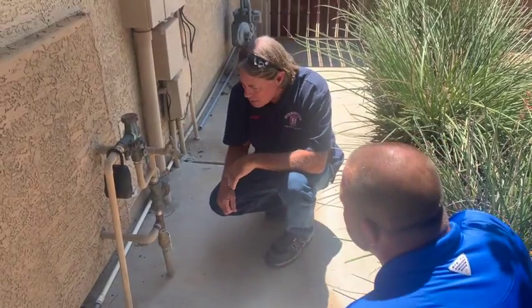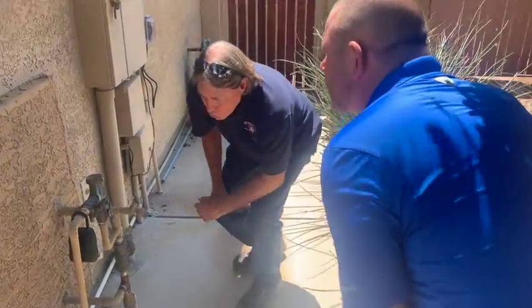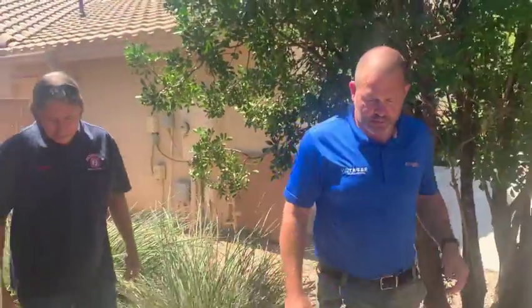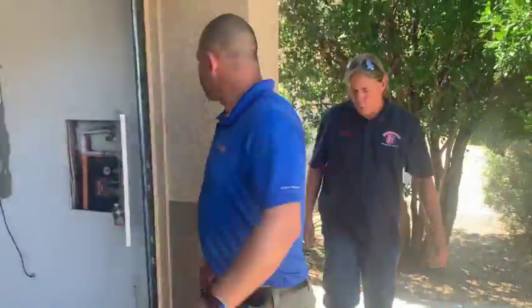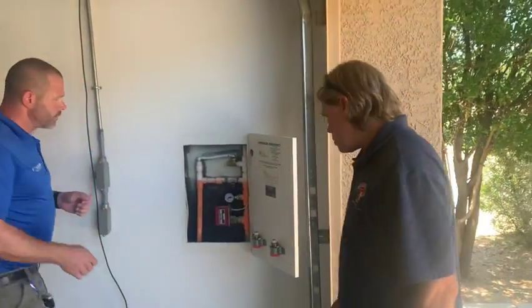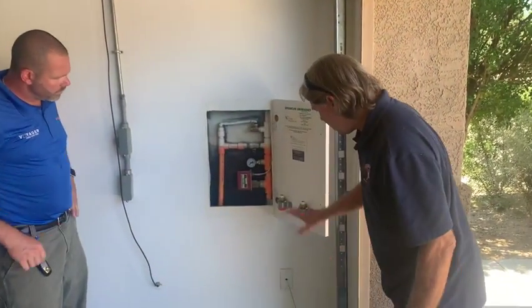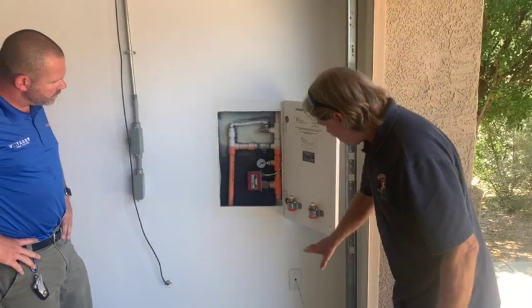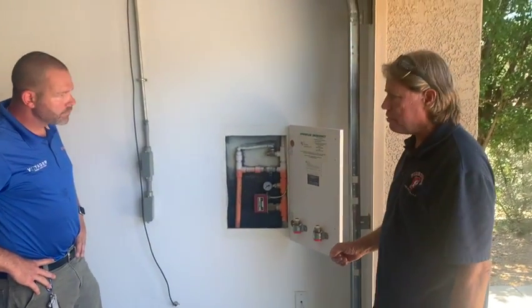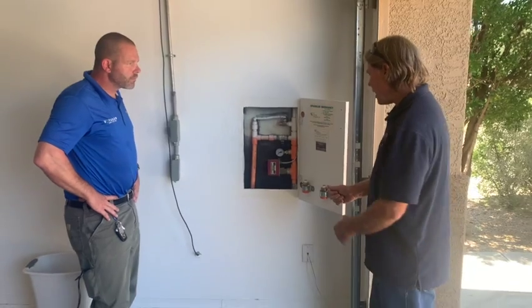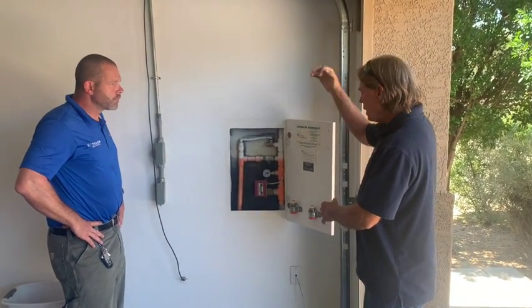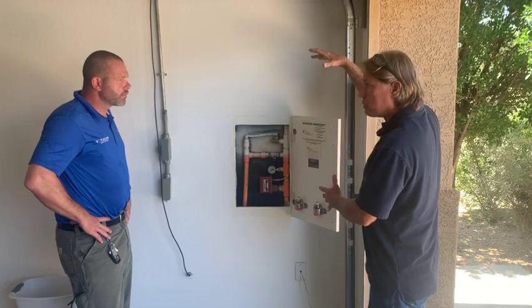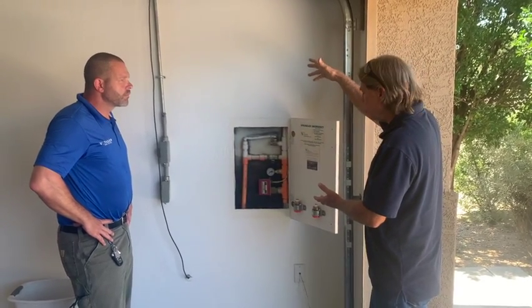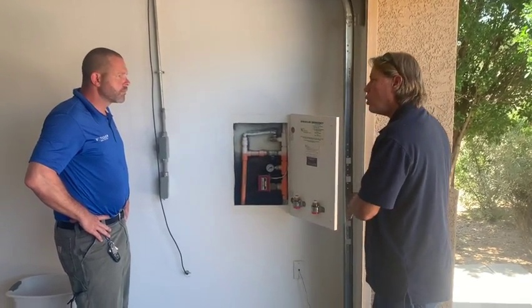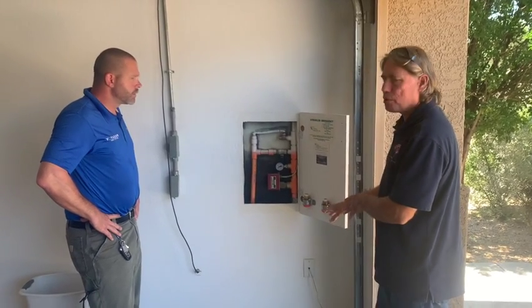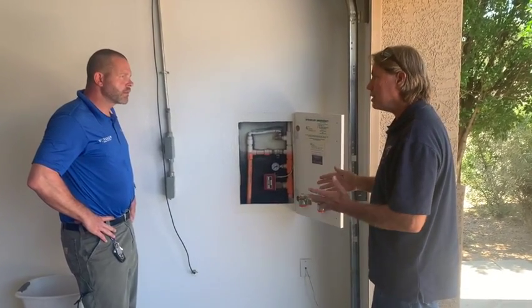Exactly. Yeah. Excellent. So from here we can go on inside if you like, and we'll look at the fire sprinkler riser receiver. Excellent. So this is where the control valves are. And in a residential setting, the first device that we're going to have in line, you can't see in the video, I'm sorry about that, but it's behind the wall. It's called a check valve. That check valve has the function of allowing the water to flow one direction only and not allow any of this trapped water that's up there for a period of time and never touched, usually, to get back into your potable water. So those check valves, it's important that they operate properly, and we'll be testing that today.